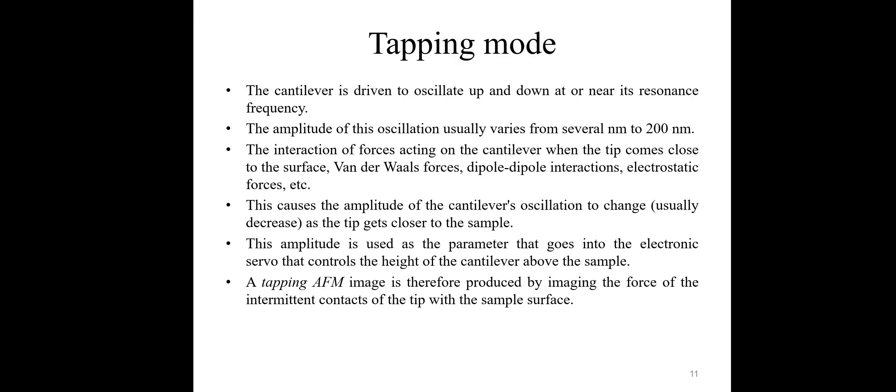In tapping mode, the cantilever is driven to oscillate up and down near its resonant frequency. The amplitude of oscillation usually varies from several nanometers to 200 nanometers. Van der Waals force, dipole-dipole interaction, and electrostatic force act on the cantilever when the tip comes close to the surface. This causes the amplitude of cantilever oscillation to change as the tip gets closer to the sample, and this amplitude parameter controls the height of the cantilever above the sample.